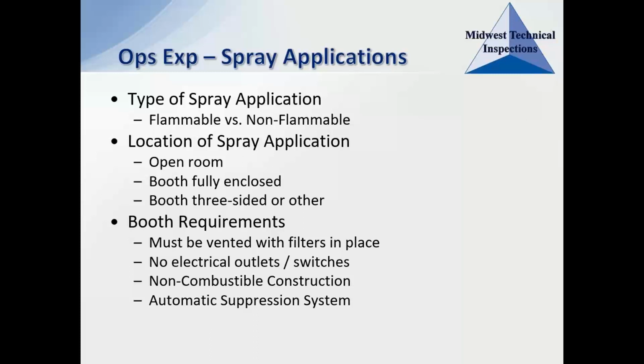So that's the first and foremost. What are they spraying? And then second, where are they doing this spraying operation? Are they just doing it out in the open room where it's exposed to other operations? Are they doing it in a fully enclosed manufactured booth? Or is this some kind of modified, or something that maybe they built their own, where it's a three-sided or other, maybe like a curtain wall or something like that, where it's not truly a manufactured booth?